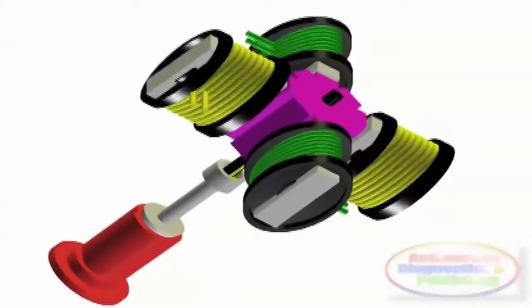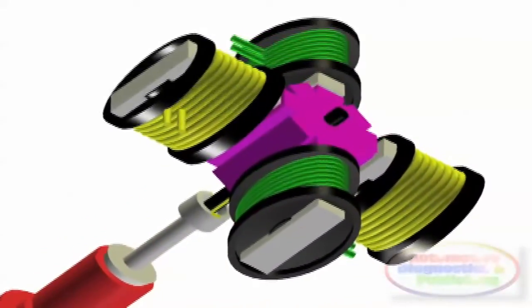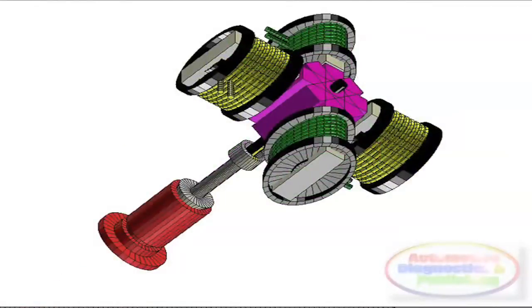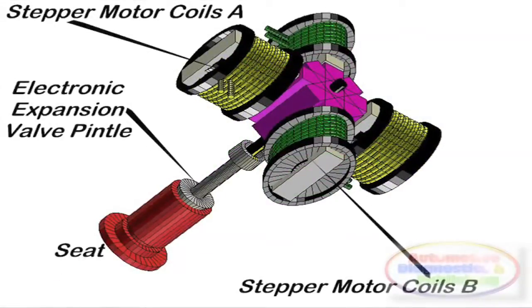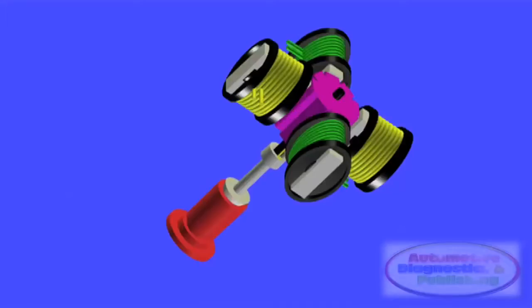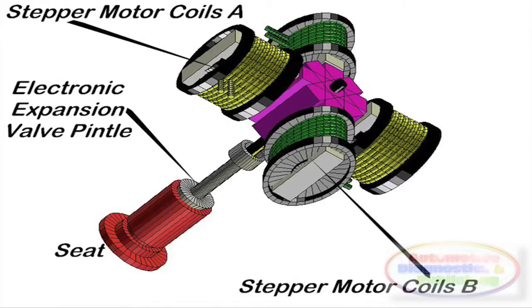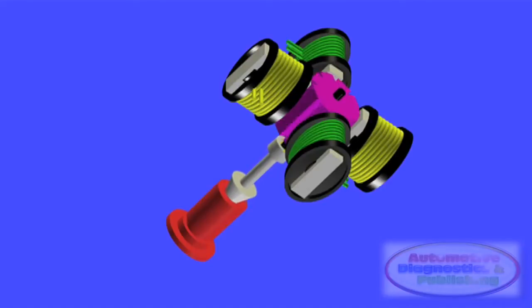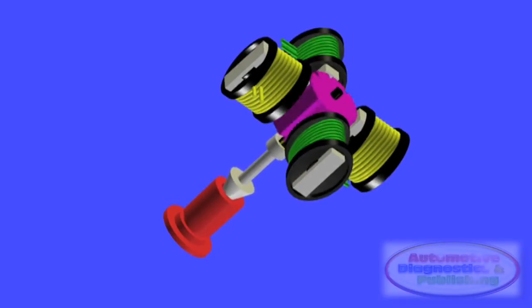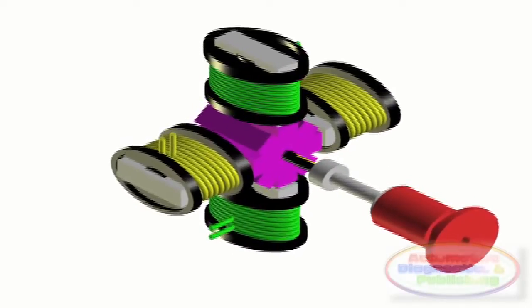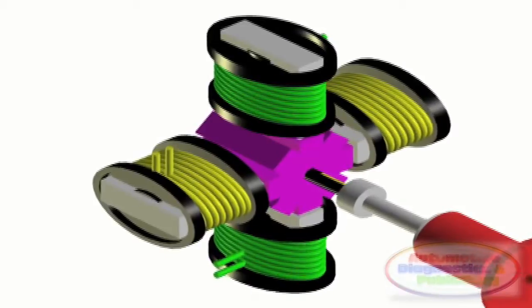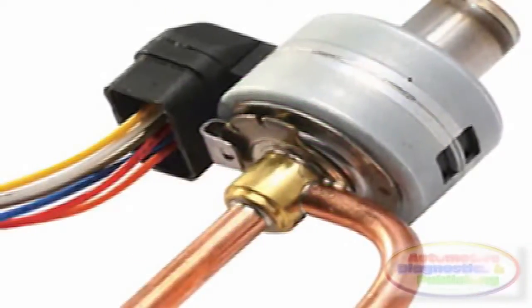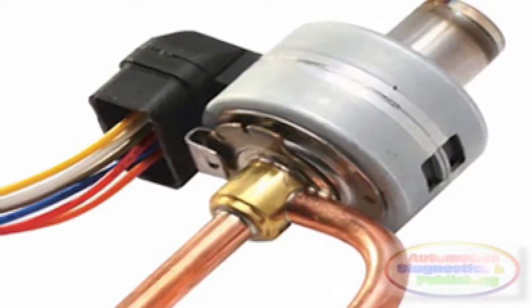The HVAC electronic expansion valve uses a stepper motor to control the valve aperture. A stepper motor is related to digital technology. It is a brushless motor, and works by the constant phasing or switching of four magnetic field coils. Here they're named coils A and B. Suffice it to say that stepper motors are used when very fine control is needed. They're used on CNC machine shop milling machines and lathes to make accurate metal parts, among other applications. This is the reason why they're also used in the HVAC electronic expansion valve.